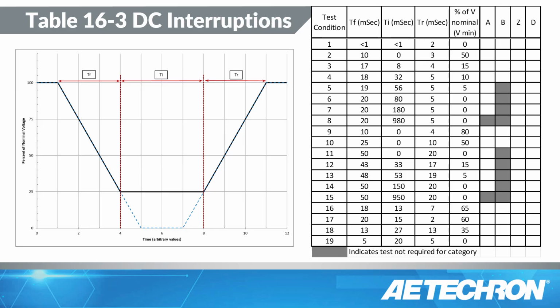Now let me look at the DC momentary interruptions test in particular here. This is where the AE Techron equipment really excels. In this test, you have a dwell time at your voltage, in this case 28 volts, let's say, and then you drop down over a specific period of time, dwell at some voltage level, and then increase over another specific period of time. And here are the test requirements that might be required of you, depending upon which category you're using. A and B eliminates some of these tests.